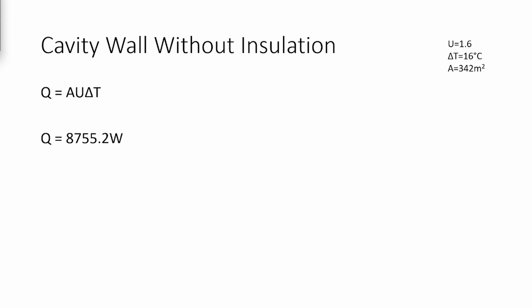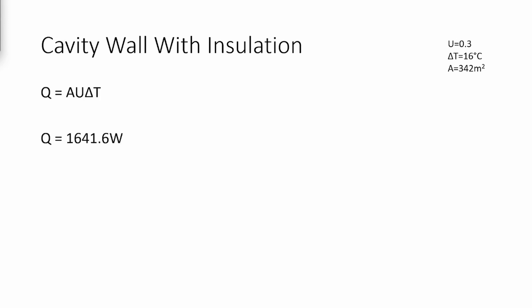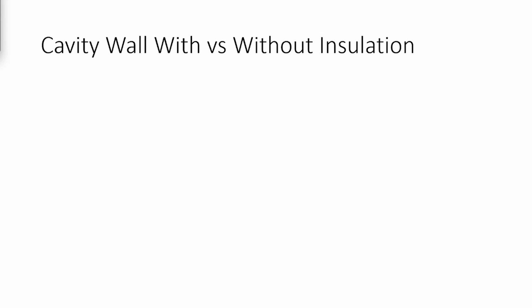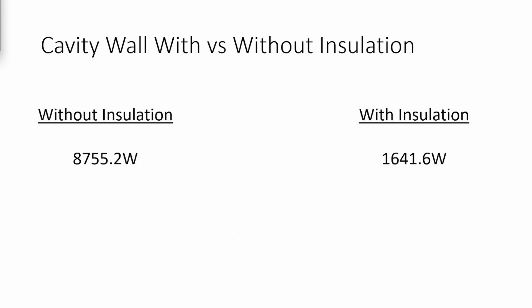If you now consider cavity wall with insulation, it has a U-value of 0.3. Using the same equation, we can see that the total heat loss is 1,641.6 watts. Comparing these two, there's a 7,113.6 watt difference.